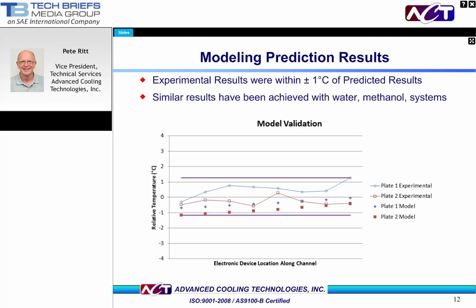We have previously stated that pump two-phase cooling systems are more complex and therefore can be more difficult to model. However, advances in modeling capability have made that less so. In the graph, we are modeling two of the cold plates from the multi-plate system described in the previous pages. The individual dots are the predicted modeling results for plate 1 and plate 2. The lines represent experimental results for those two plates. Good agreement within 1 degree C is shown between the modeled and measured results for both cold plates. Note also the excellent temperature uniformity across both of those cold plates.